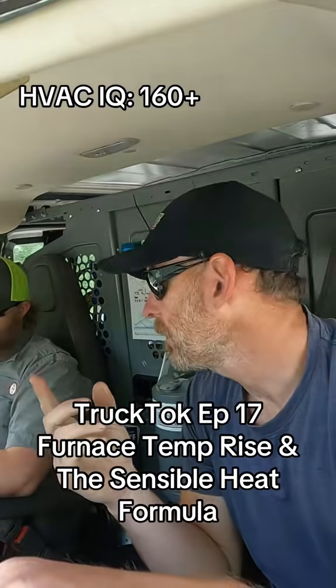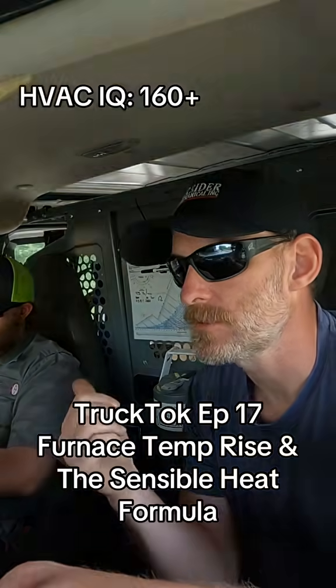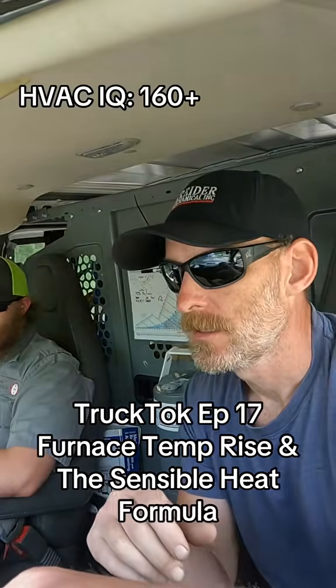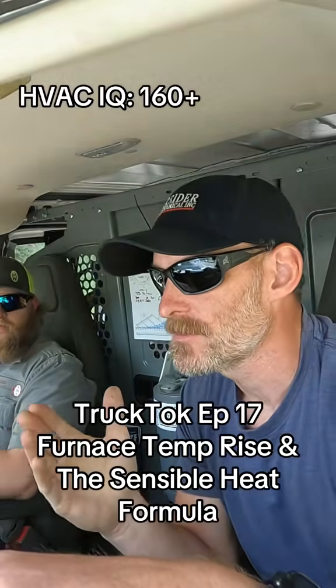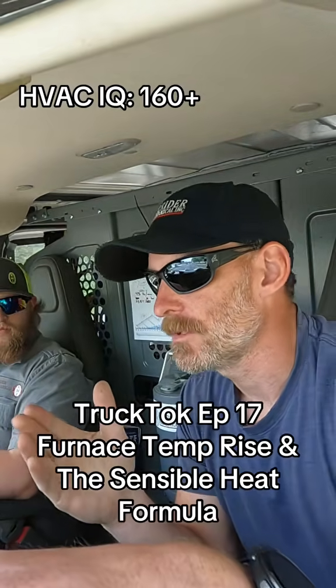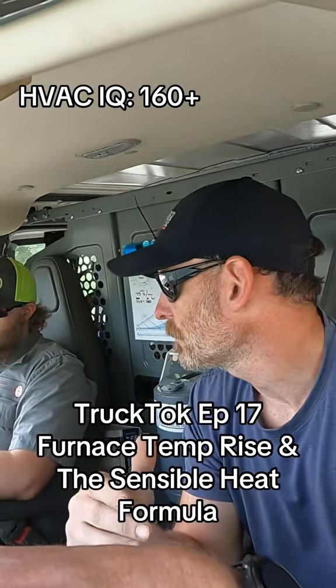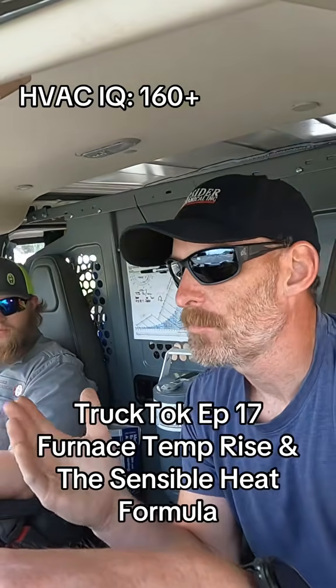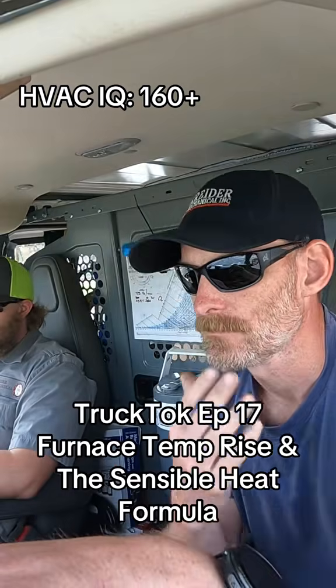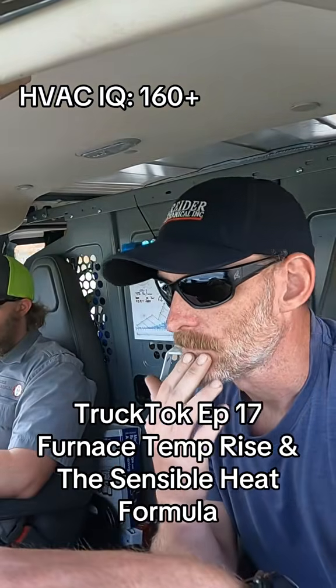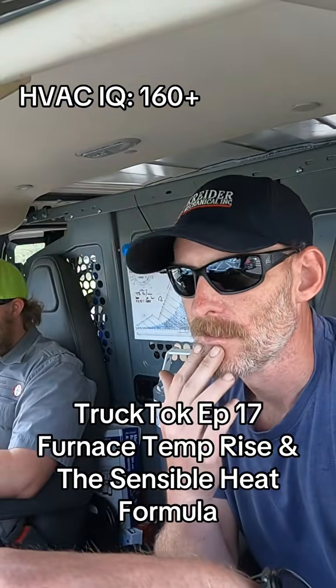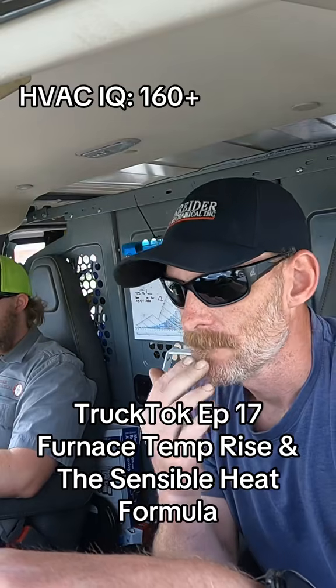We were working on that furnace yesterday, and we were talking about the temp rise, right? Yes. The temp rise on that Trane RTU for heating was 25 to 55 degrees, wasn't it? Yes. Why did they put that on the nameplate? So you can see if there's low airflow or not.